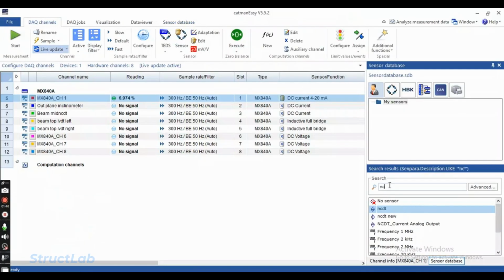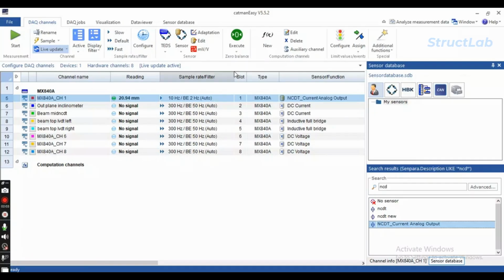Back on the channel assignment screen, search for your newly created sensor profile in the database panel. Then double-click or drag it to assign it to channel 1. With the sensor profile assigned, the live measurement instantly updates to show active current readings. Click Zero Balance to tare the baseline. As you physically displace the laser target, observe the real-time displacement values updating in catmanEasy, confirming a successful configuration. Your sensor is now ready to record live displacement data during testing.